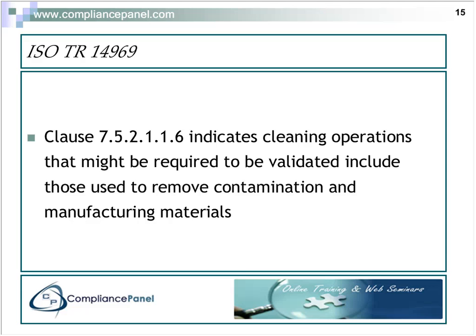And it does say that cleaning operations that might be required to be validated include those used to remove contamination and manufacturing materials. So if you have a manufacturing process that requires the use of some kind of manufacturing material to expedite it, and some examples might be things like mold releases.